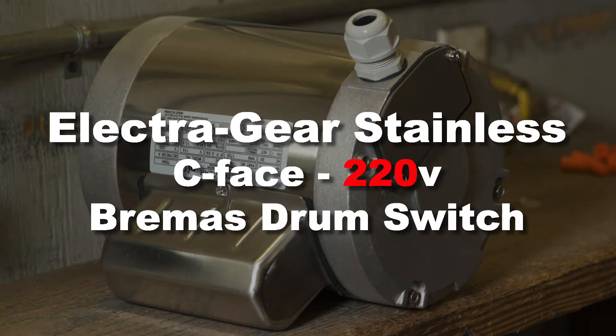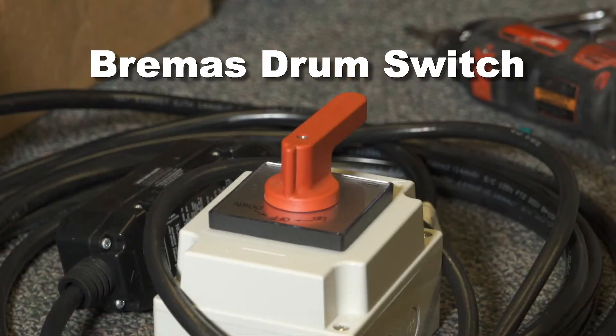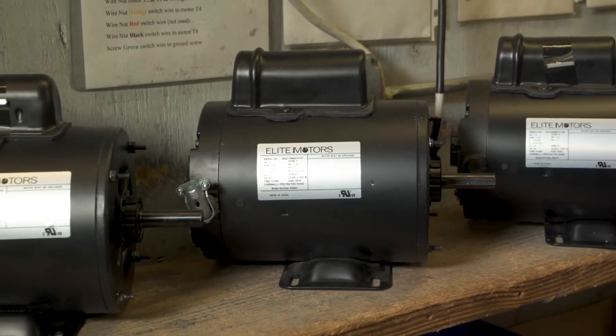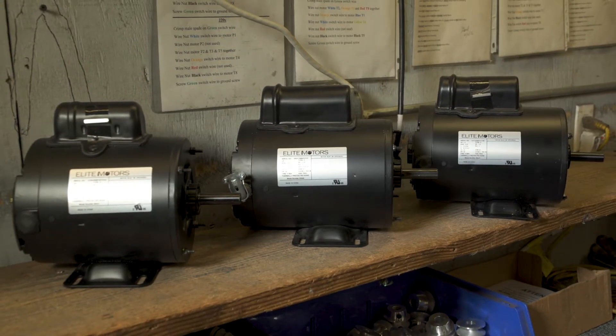In this video we're going to show you the procedure for wiring the ElectraGear Stainless C-Face motor for 220 volts to the Bremas brand drum switch. Bremas brand switches with red handles are supplied by BHUSA. They are NEMA rated up to 20 amps and can be used on any BHUSA supplied single-phase reversible AC boat lift motor from three-quarter horsepower through one-and-a-half horsepower, both 110 volts and 220 volts.